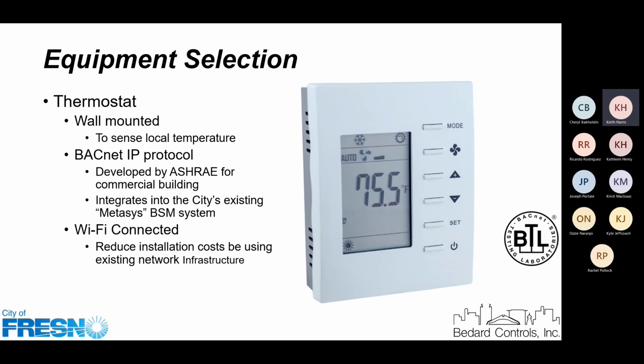So the reason this was selected is it's a low-cost alternative to a full building management system, and it works nicely when we have what we refer to as rooftop package units or rooftop split units, and we are basically turning those on and off based on the set point and the schedule. So what we do is we take off the existing thermostat, and we have a technician doing that as we speak. We take off the existing thermostat and we replace it with this one that you see in the picture.